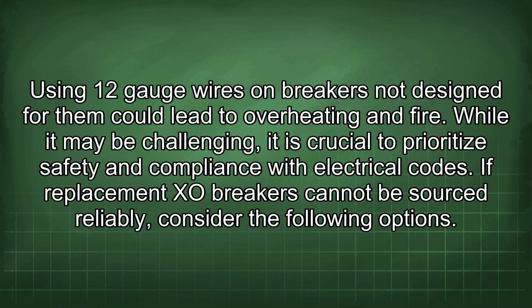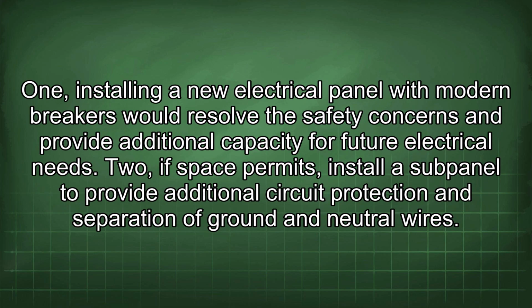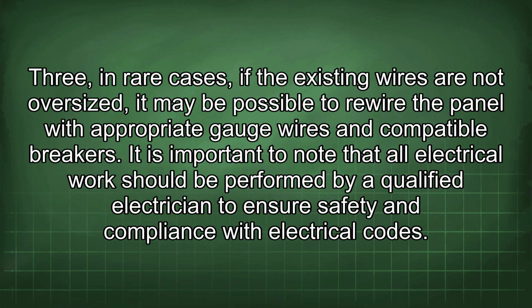If replacement XO breakers cannot be sourced reliably, consider the following options. 1. Installing a new electrical panel with modern breakers, which resolve the safety concerns and provide additional capacity for future electrical needs. 2. If space permits, install a subpanel to provide additional circuit protection and separation of ground and neutral wires. 3. In rare cases, if the existing wires are not oversized, it may be possible to rewire the panel with appropriate gauge wires and compatible breakers.